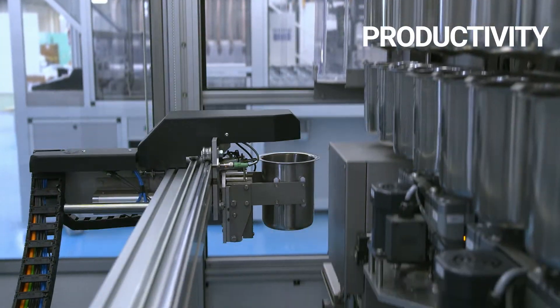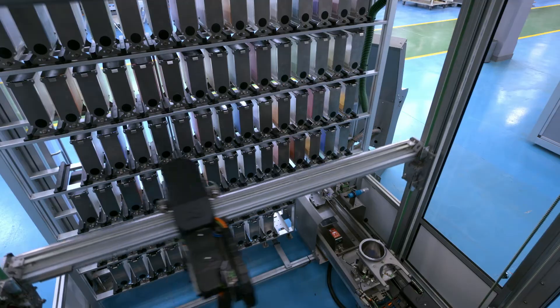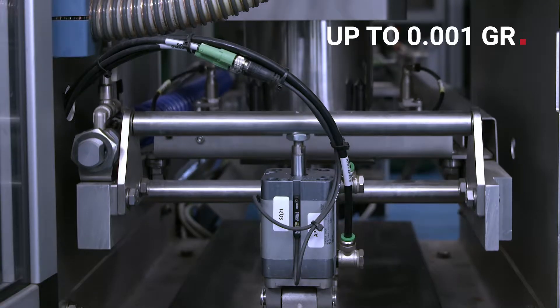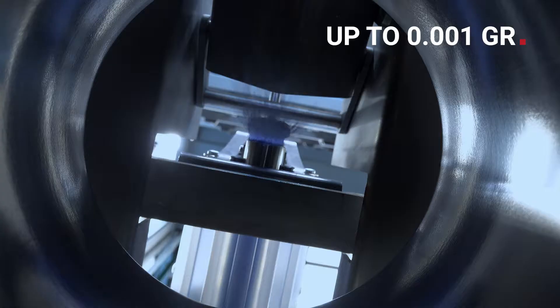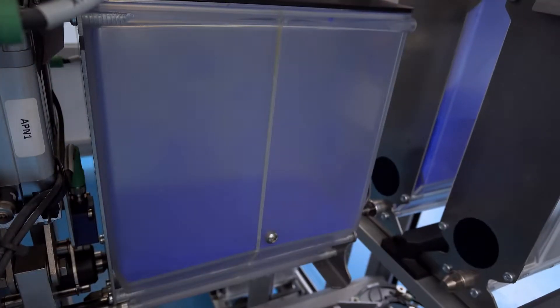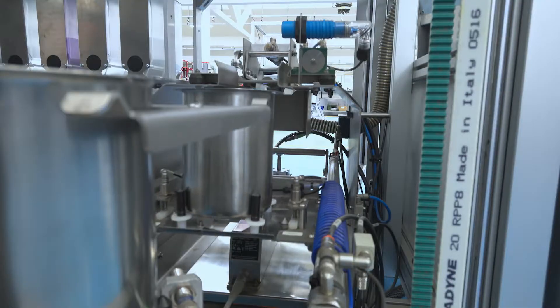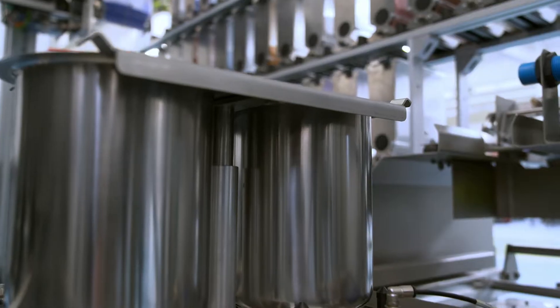Two three-axis robotic arms handle the mini silos and the buckets. The weighing station is equipped with scales calibrated to 0.001 of a gram. An efficient suction system with Venturi technology allows the weighing area to be kept clean and avoids any internal contamination.